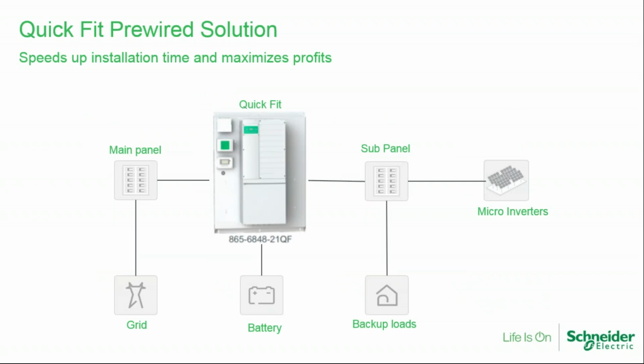A Quick Fit can be substituted in this case, and it basically has a monitor on it, and it's all pre-wired. So basically, you connect to the batteries, you connect to the grid, and you connect to the sub panel, and you're done. And I think the timing that we did on some of these was that it took about 10 minutes to do the install. So that means you can do multiple installs in a day.